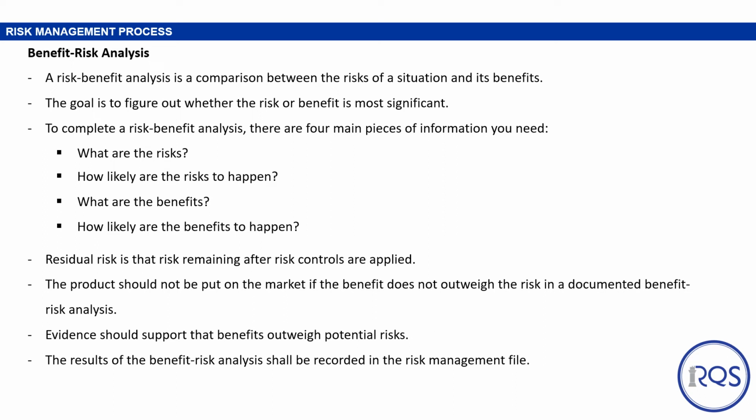If the evidence does not support that conclusion, then the manufacturer may consider modifying the device or its intended use. Evidence can come from data or clinical literature. And if there's not any evidence, if there's nothing to justify that the benefits outweigh the risks, then that risk would be unacceptable. The results of the risk-benefit analysis should be documented in the risk management file.